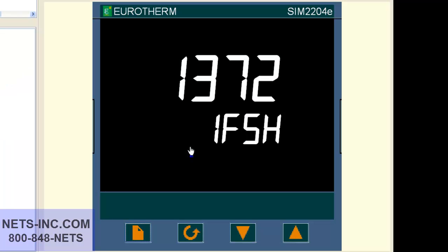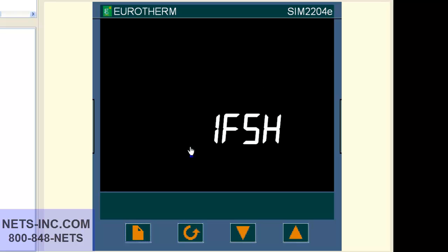This video tutorial will show you how to change the alarm state action from normally open and closed in alarm to normally closed and open in alarm on a Eurotherm 2200 series controller. The controller is set up as alarm number 1 is a full scale high FSH and it is assigned to the AA relay. We are going to change the AA relay sense of output from normal NOR to inverted INV.